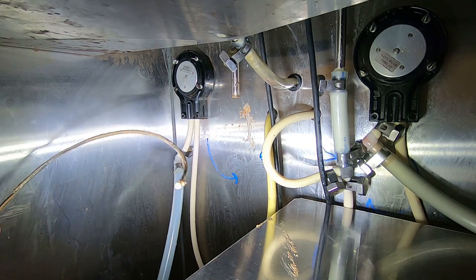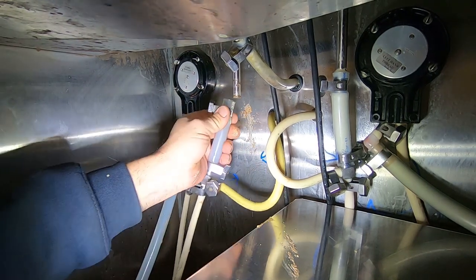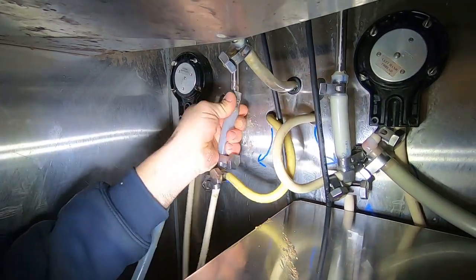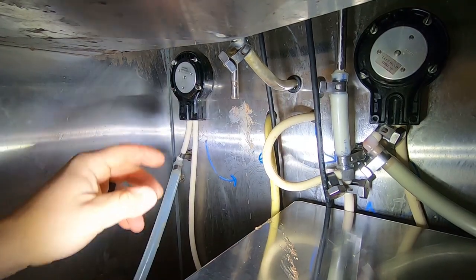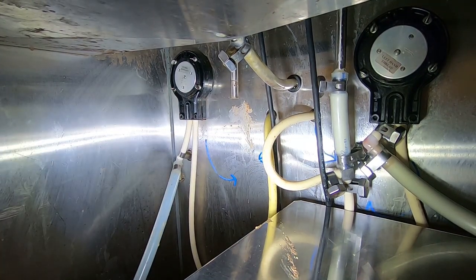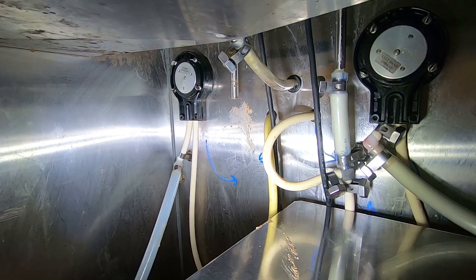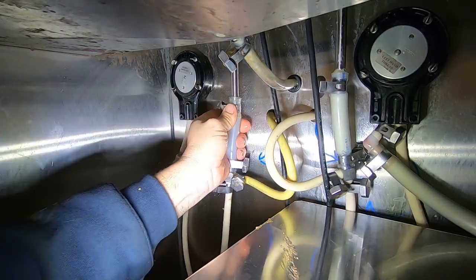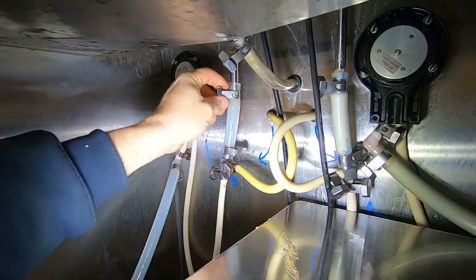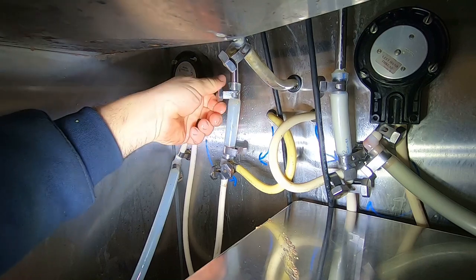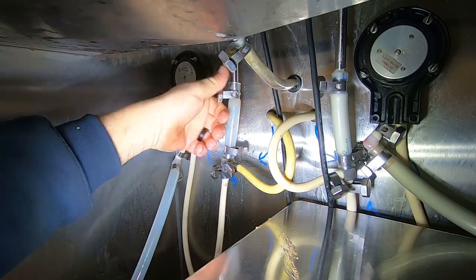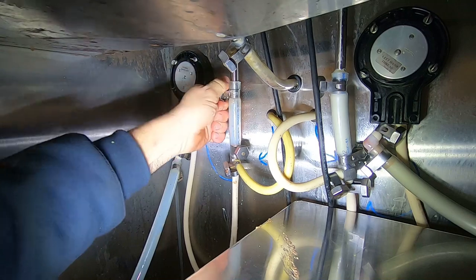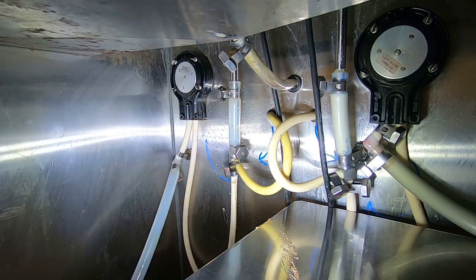Yeah, I'd say we're just gummed full of crap. Since we've got water pumping out on the one side that's going up to there, it should make it all the way up to the top. We'll run cleaning solution through here. It's got milk stone dissolver and all that in it, and these are certified to be cleaned in place. They might not be using as strong of a solution.